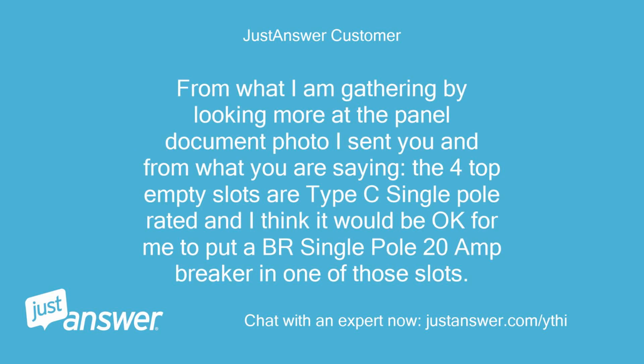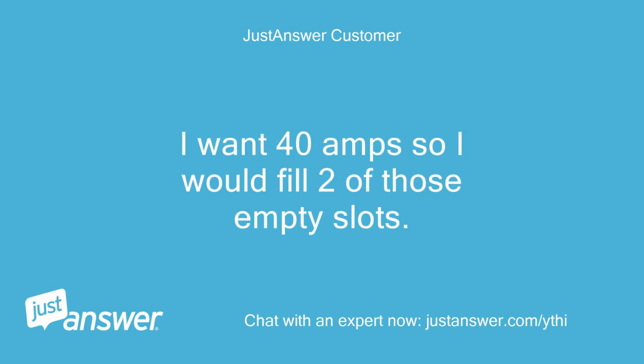From what I am gathering by looking more at the panel document photo I sent you and from what you are saying, the 4 top empty slots are Type C single pole rated, and I think it would be okay for me to put a BR single pole 20 amp breaker in one of those slots. I want 40 amps, so I would fill 2 of those empty slots.